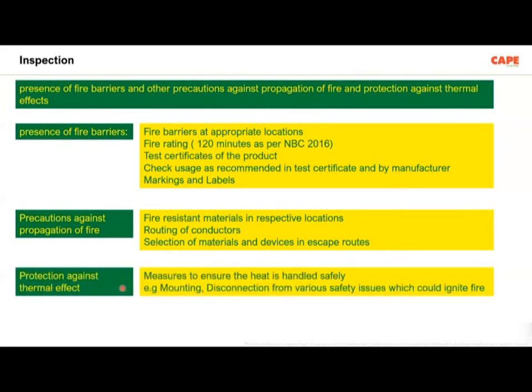Number 3, protection against thermal effect. As I said, you will have some equipment which is producing heat. Have you installed that equipment in such a way that the heat produced inherently because of the operation of the equipment is not destroying the neighboring installations? So all these 3 parts come under fire inspection. So the sequence: fire barriers with 5 parts, precaution against propagation of fire, and protection against the thermal effect. All the 3 are important.